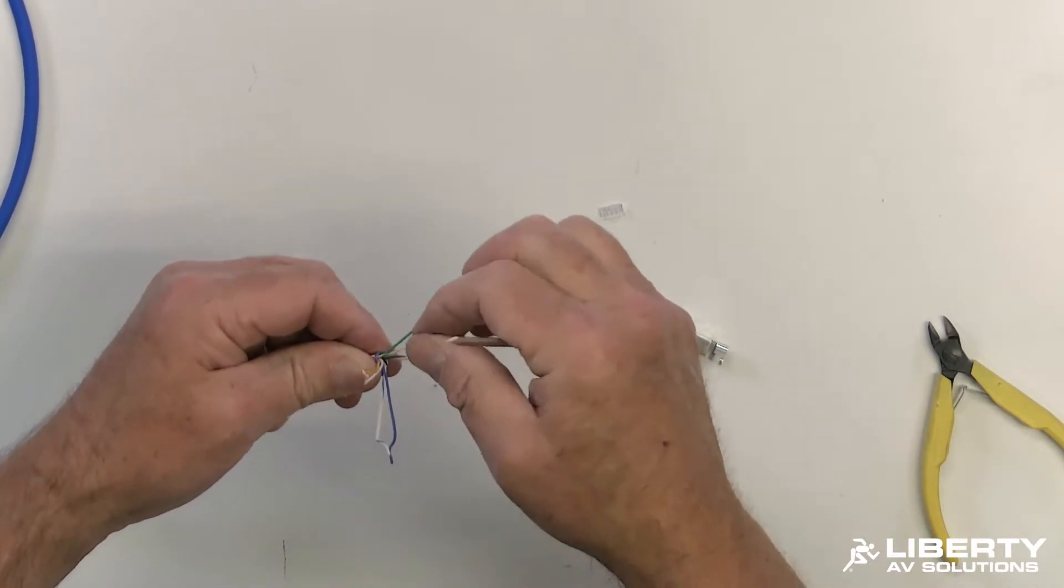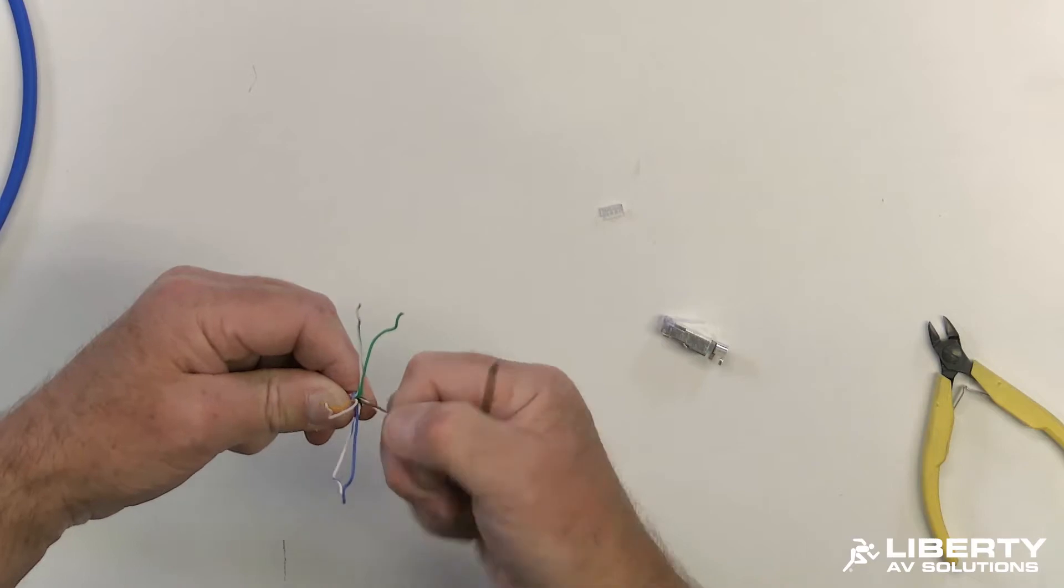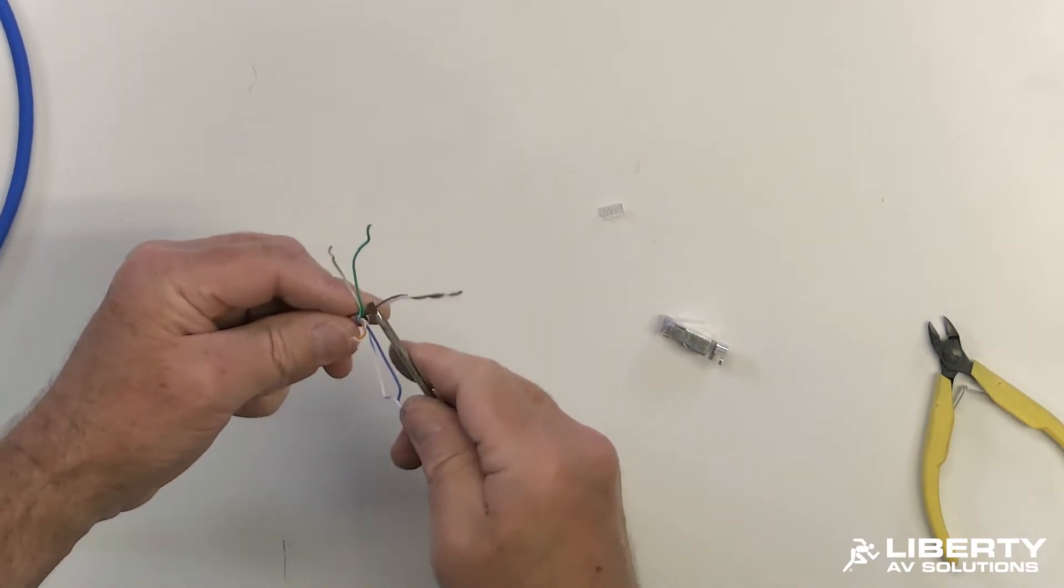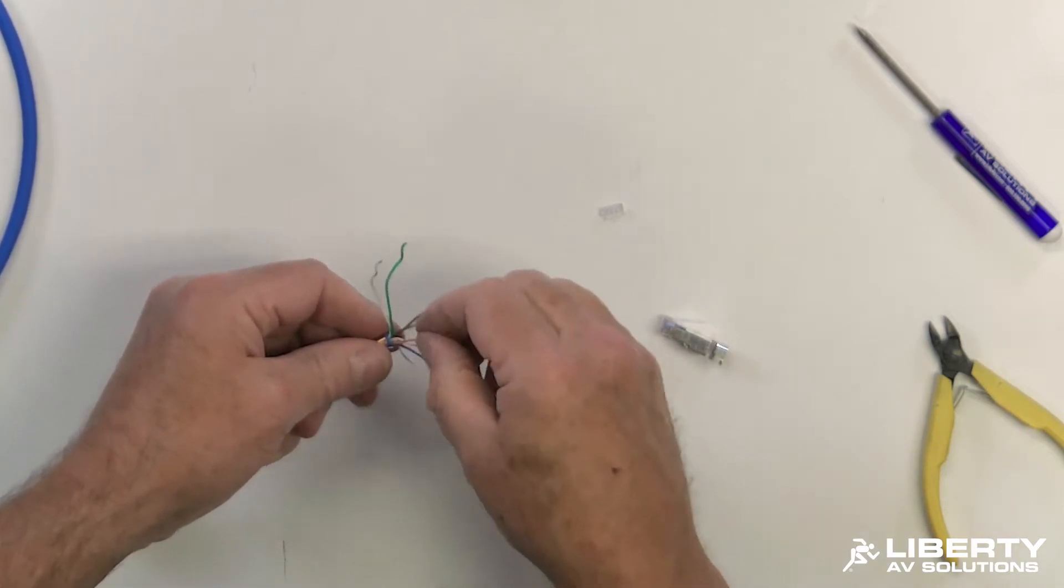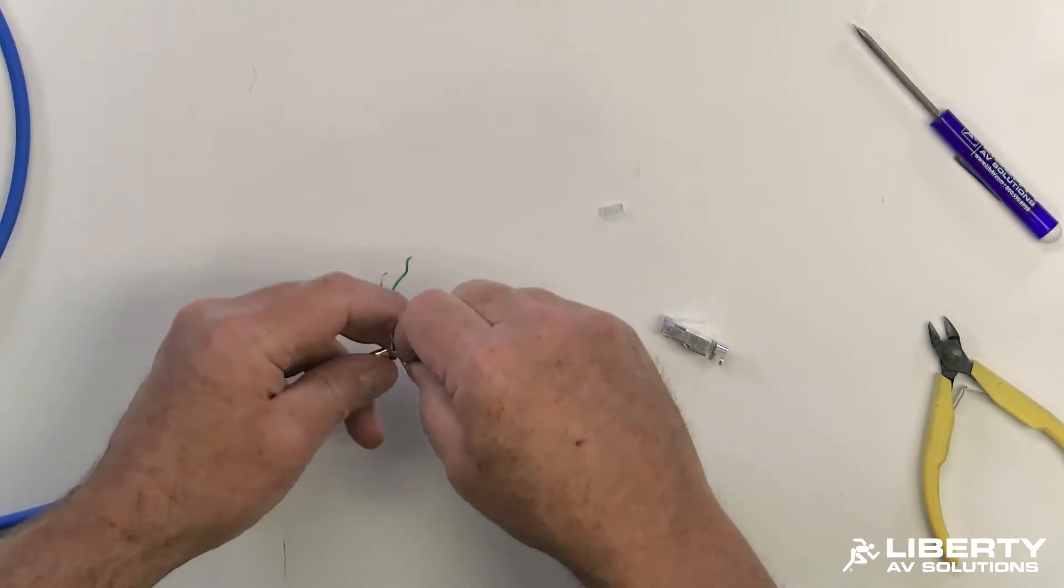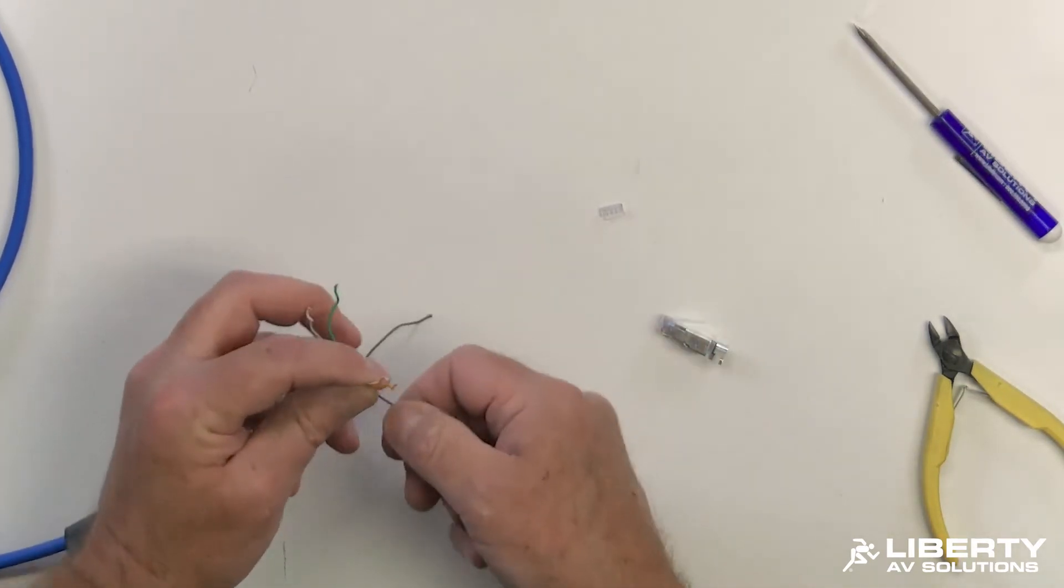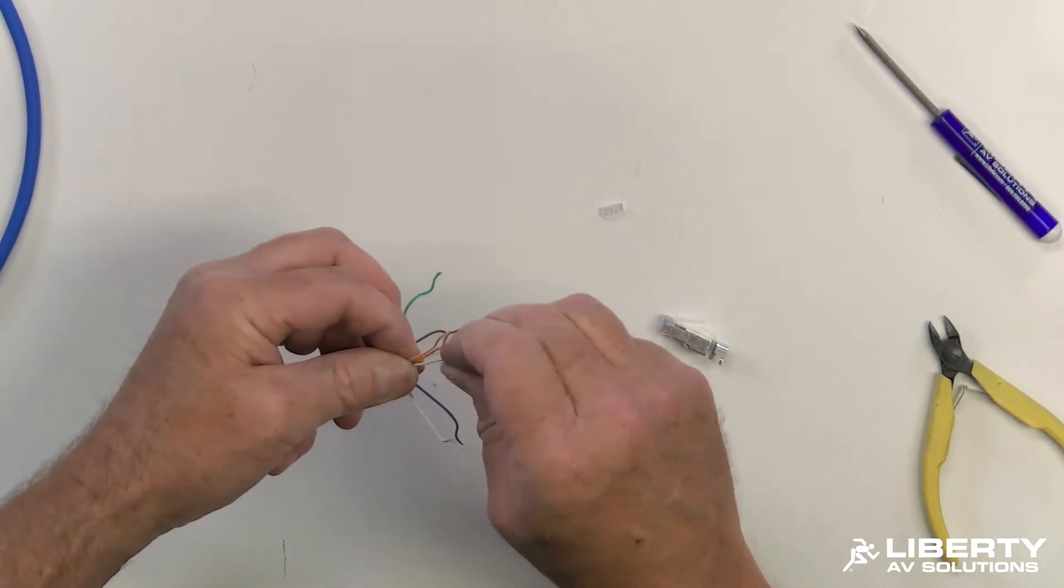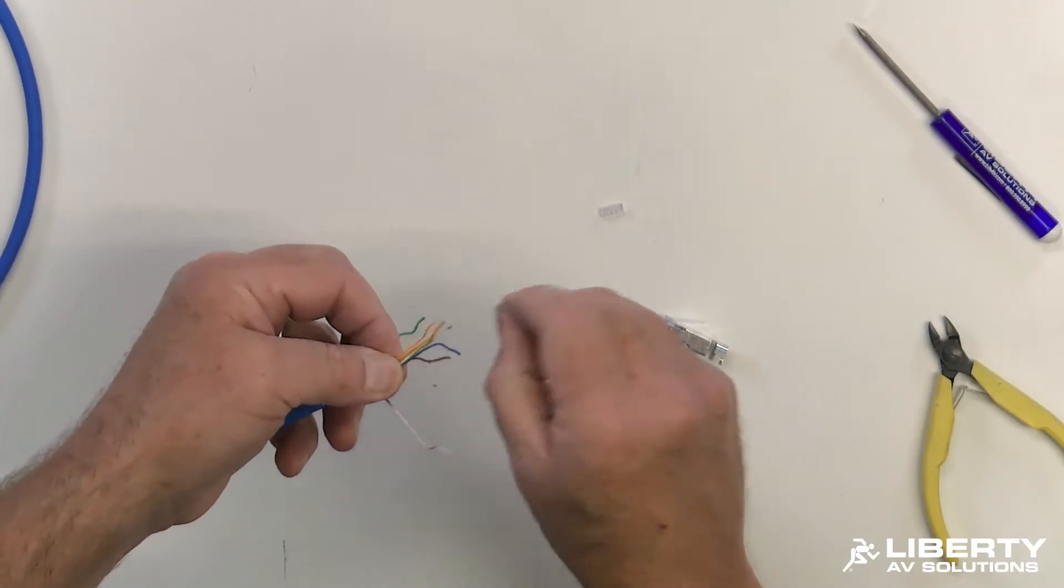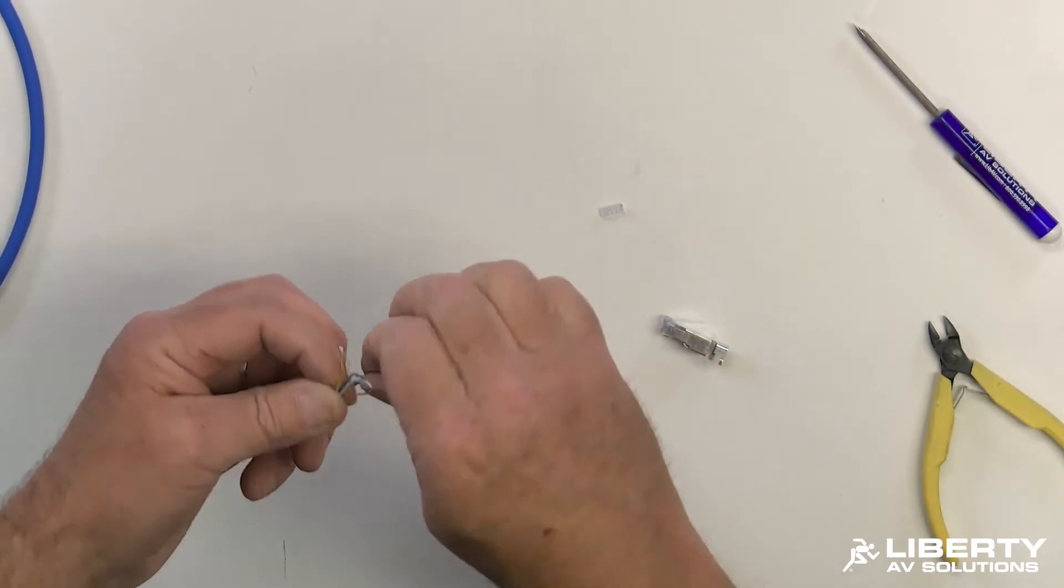Go ahead and just go down and untwist all four pairs. Don't want to pull too tight or else you could actually damage the insulation. Alright, so I've got all my pairs separated. I'm going to put these in the appropriate color code. We're going to do 568B because that is generally the industry standard for data type communications.